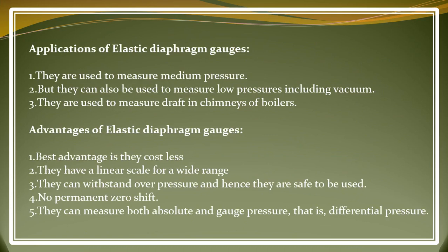So let's talk about applications of the elastic diaphragm gauge. They are used to measure medium pressure, but they can also be used to measure low pressure including vacuum. They are used to measure draft in chimneys of boilers. Now let's talk about advantages of elastic diaphragm gauges. The best advantages are they cost less, they have a linear scale for a wide range, they can withstand overpressure, and hence they are safe to be used. No permanent zero shift. They can measure both absolute and gauge pressure, that is differential pressure.